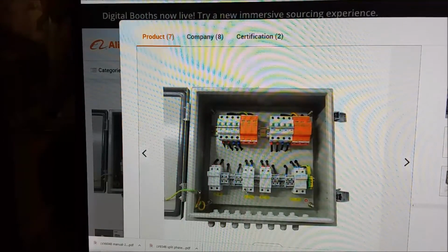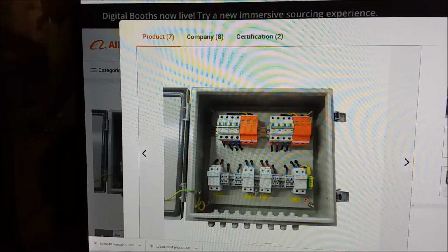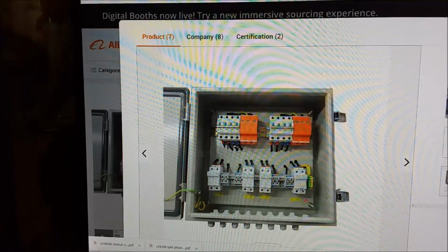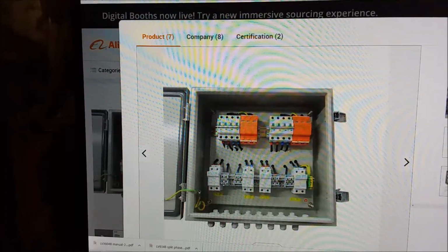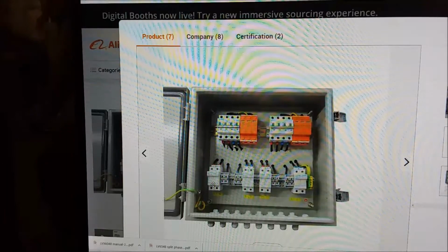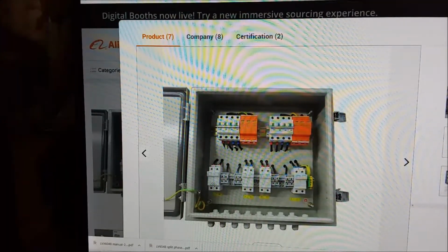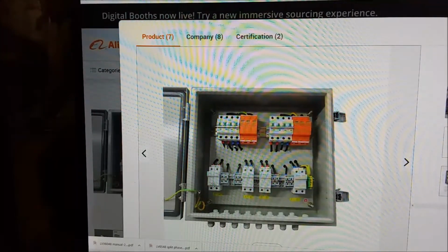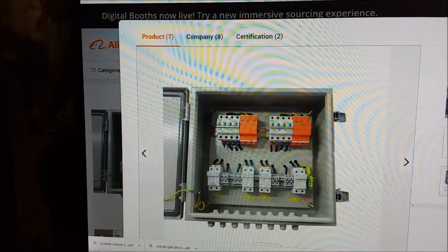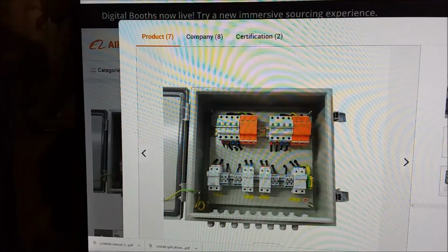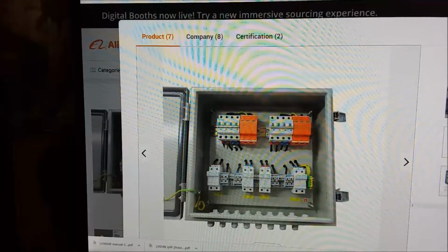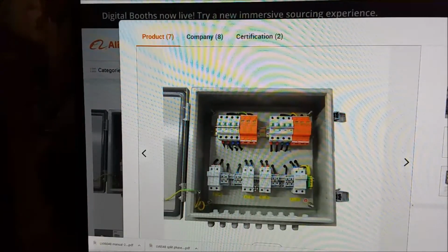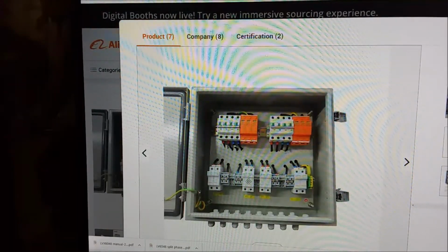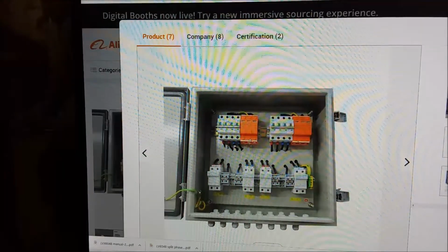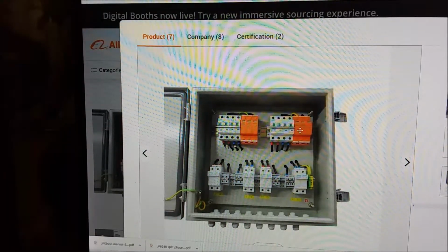Okay, at the bottom we have the photo panels coming in. Two strings, that's panels in series, and two more strings of panels in series, so you have four strings. For my setup, that would take 6 in a row. I can't put that kind of power into the inverter because it's way past the inverter's capacity I'm looking at. But since this is separated, I can run this set here into one inverter and the set over here into the other inverter.